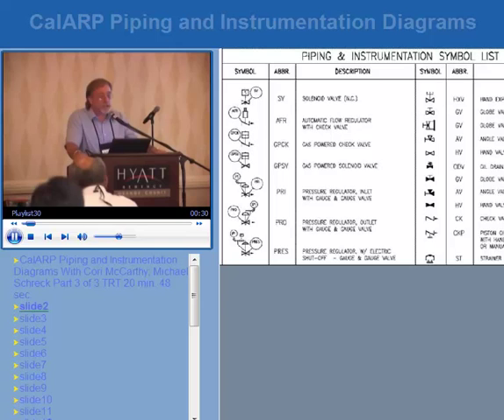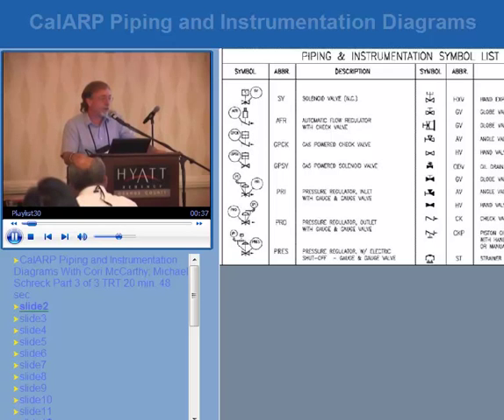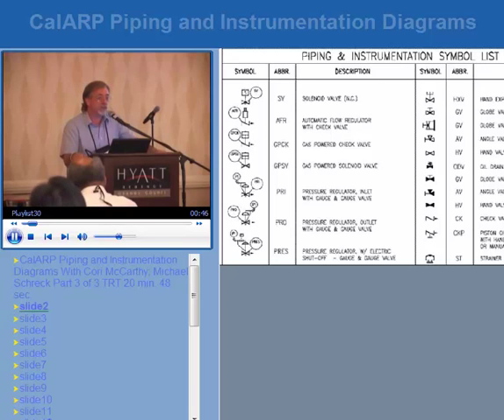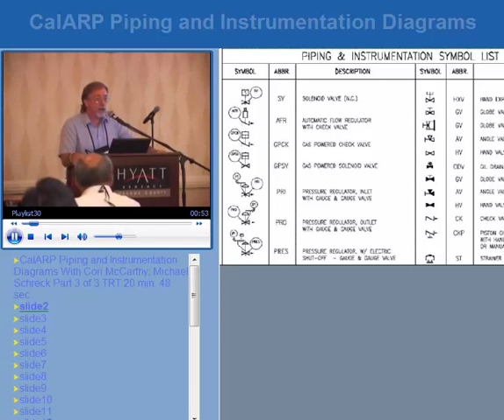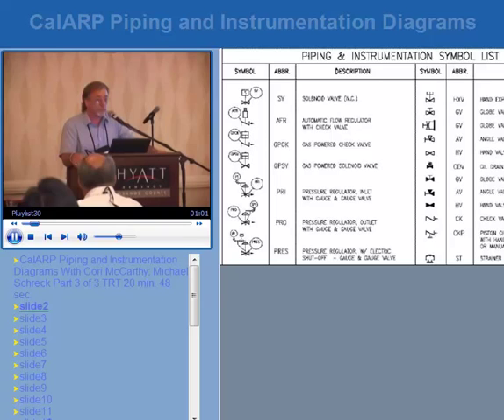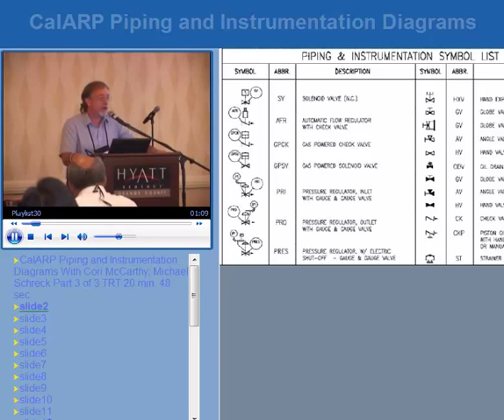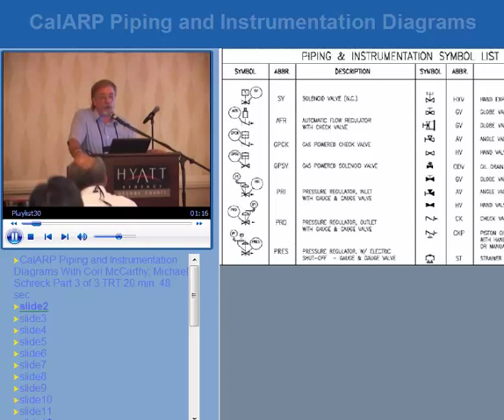System entry is a very simple, one-page means of controlling the system — making sure it's pumped out and 'flat' — then putting valves in the right position when going back online. In Iowa this year, a meat processing plant had a contractor who put in a new liquid line, went into the engine room, and opened the liquid line without verifying other valves were in the proper position. He didn't pressure test the system as required and blew liquid ammonia over 15 people. One person passed away. We have fatalities on an annual basis in the U.S. with ammonia.